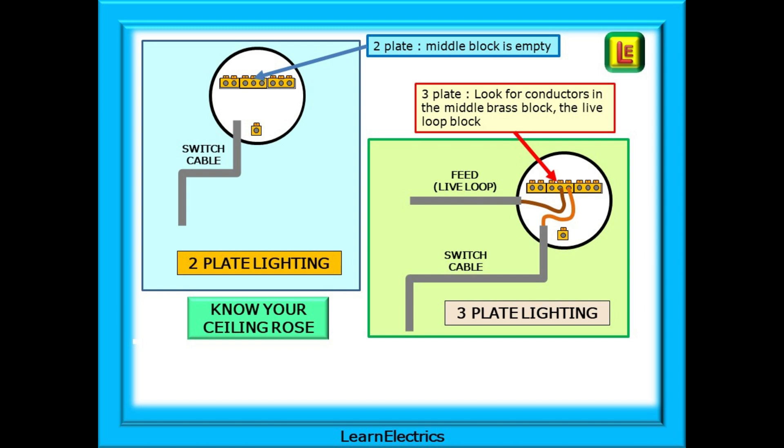Whether it's twin and earth or singles, take a look at the middle brass block, the live loop block. In a two-plate system this middle block should be empty, whilst in a three-plate system there will be at least two conductors in this middle block.